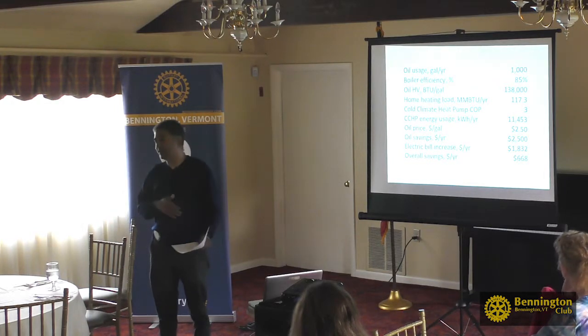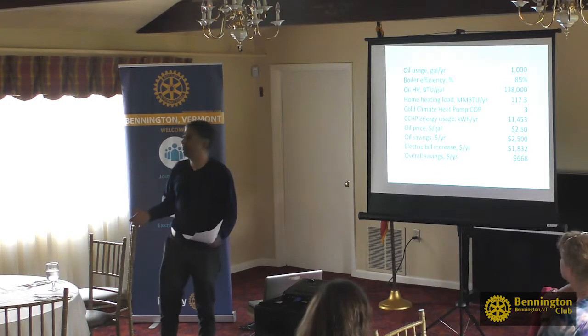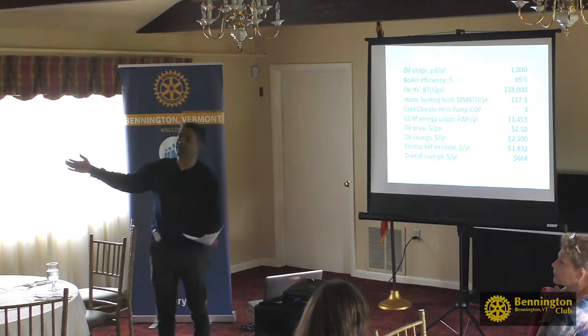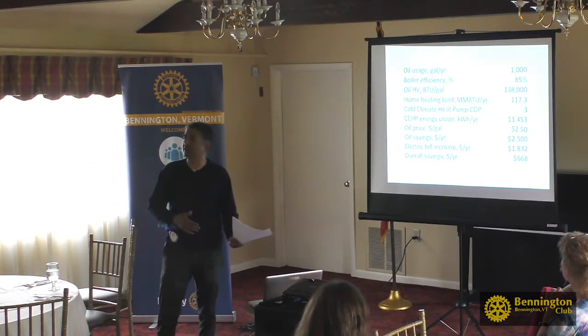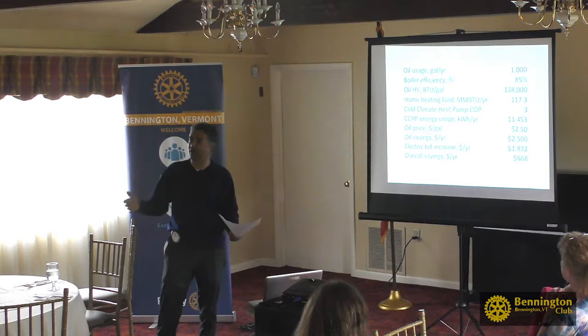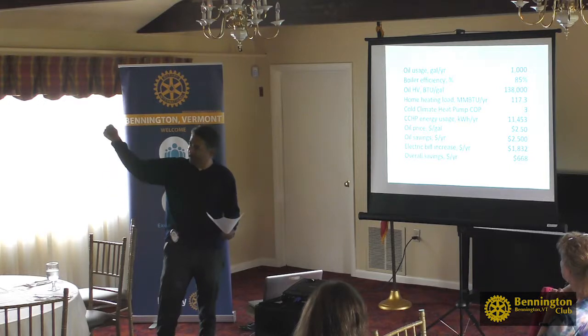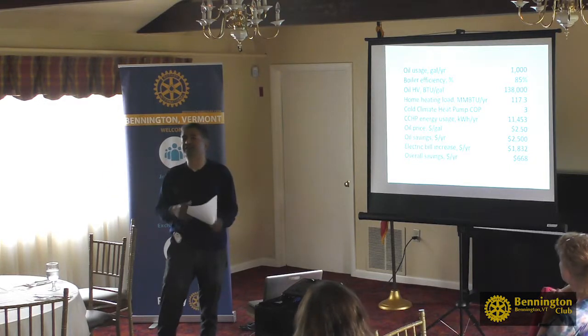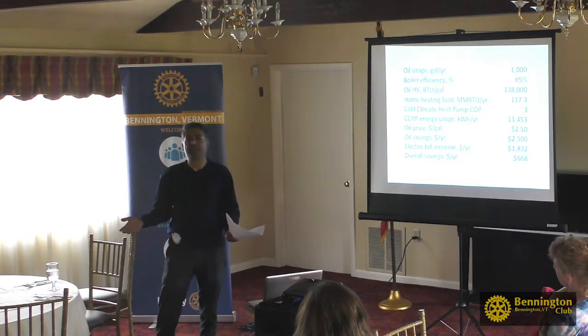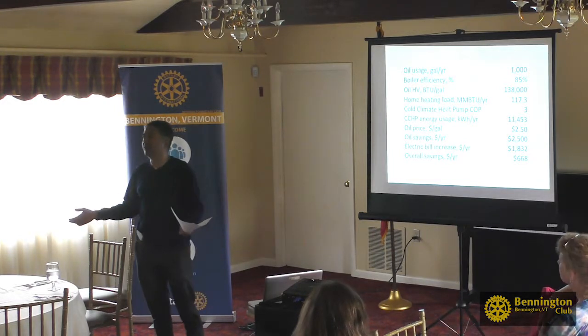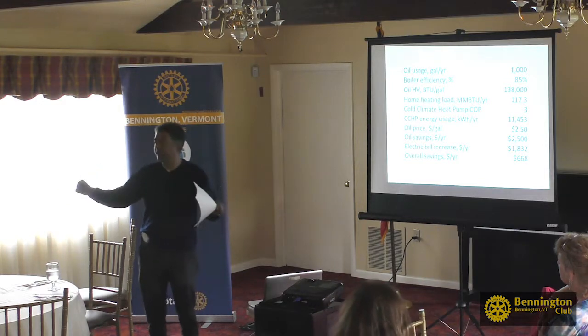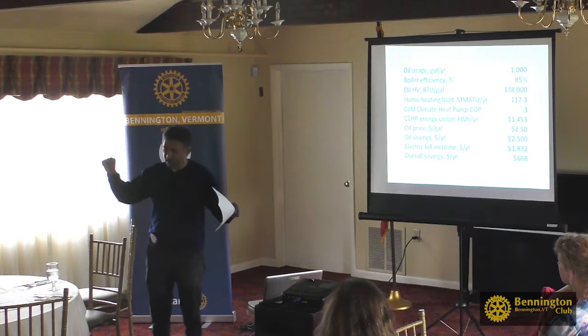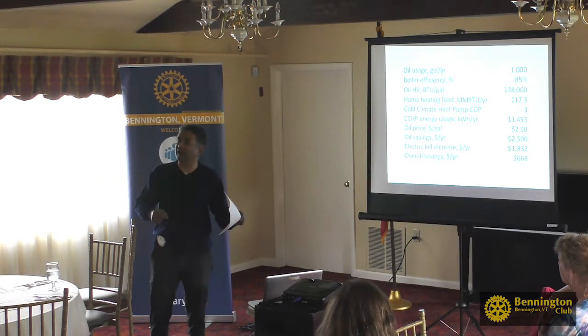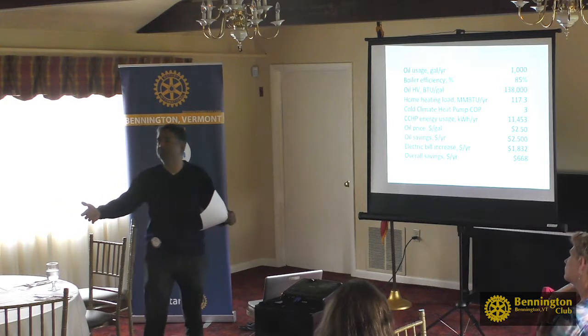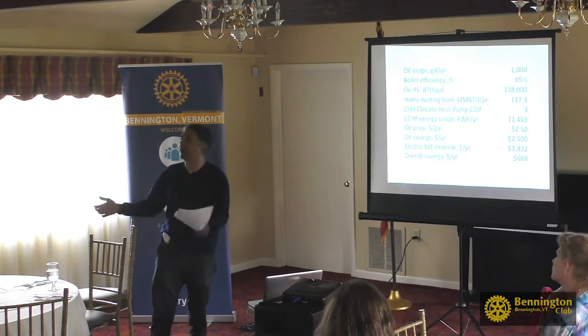So the COP, that efficiency does not stay constant. It changes as the outdoor temperature varies. The warmer it is, the higher the efficiency is, to the point where when it's down to 5 degrees or so, or I think basically if it's down into the 20s and so forth, its efficiency keeps dropping, and at some point it matches that of an electric resistance heater, right? With an electric resistance heater, it's just a coil of wire, you plug it into the wall and when it's running, if it consumes 1 kilowatt hour of electricity, it will give you 1 kilowatt hour of heat, right? That's how electric resistance heaters work.